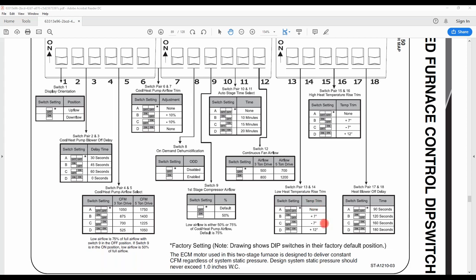Should you want, you can go an increase of 12 degrees or decrease it by 7. All right, and again, those are approximate degrees. It's not going to be exact. Those were done at the factory in their controlled lab, and that is what they found. That is all on first stage. Second stage gives you the option to do it also, so you can increase or decrease your temperature rise on second stage should you like. Again, that is all on your setup, installer, service, and application.